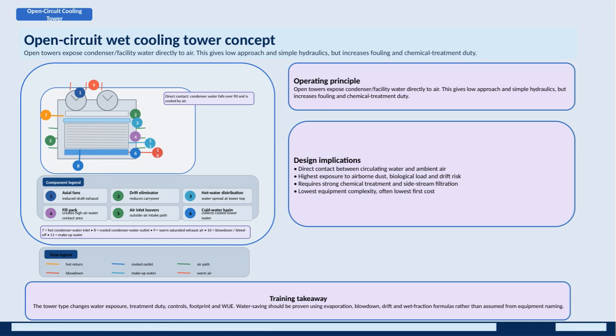The operating principle here is straightforward. The condenser or facility water is exposed directly to the air. This direct contact is what cools the water as it falls over the fill material, maximizing air-water interaction. This design offers the advantage of a low approach temperature and simpler hydraulics, which often translates to lower equipment complexity and upfront costs. However, because the circulating water is open to ambient air, it is more susceptible to fouling from dust, biological contaminants, and drift. This means that chemical treatment and side stream filtration become critical to maintaining system performance.